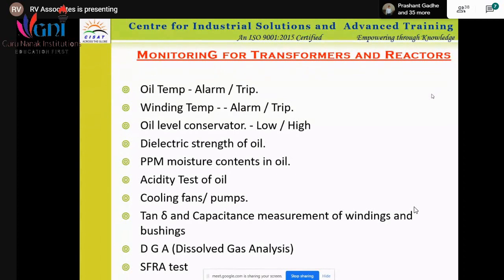Monitoring can be done, like oil temperature. Now there are two things: one is the alarm, another is the trip. When to give the alarm, when to give the trip? Just a standard practice is there that we allow the transformer temperature to rise to around 90 degrees. So there is a margin of 85 to 95 degrees. What is 85? What is 95?